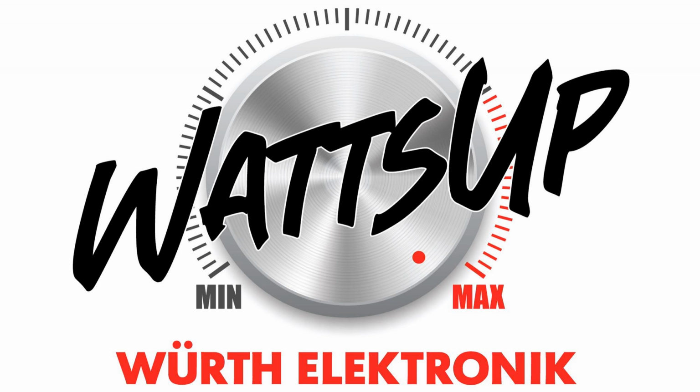And after 1 hour of continuous application of the rated voltage, we measure the parameters again, and there must be no deviation between them. So no alteration is allowed. And during the test, also the current is monitored to see if there are some sparks or some current leakage in the windings, which could be an indicator of having a fault inside the component.